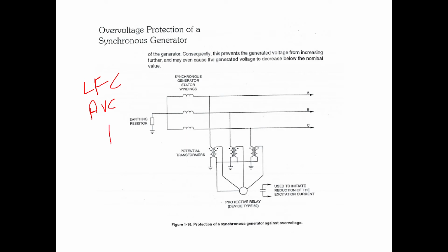But it is possible that these controllers are faulty, or you have bypassed the controller and are now using manual operation. Due to these reasons, there is always a possibility of over voltage in a synchronous generator. And what will happen if there is over voltage? It will damage the insulation of the generator. Another reason is loss of load. A sudden loss of load will also lead to over voltage of the generator.